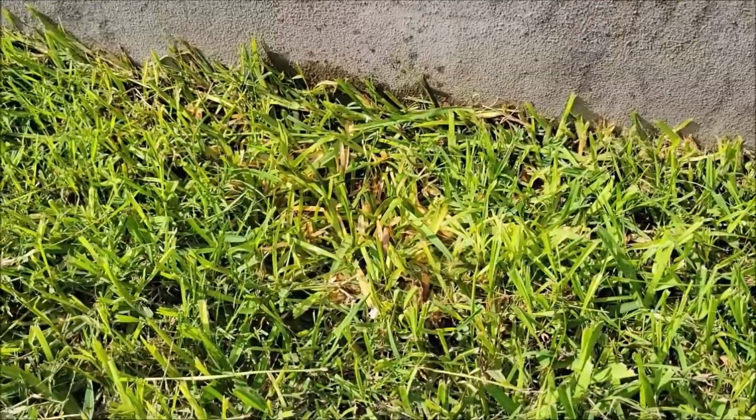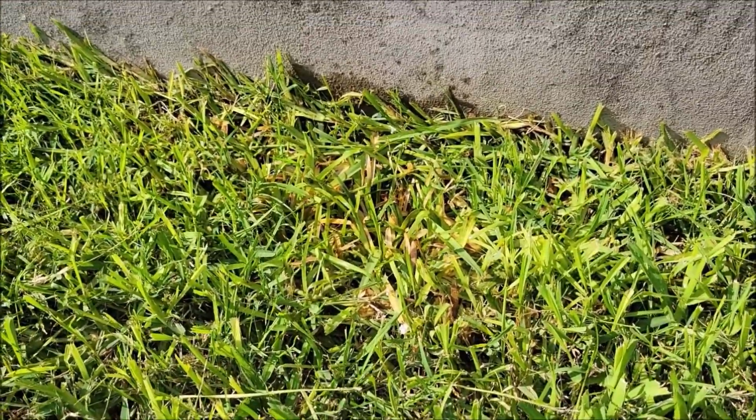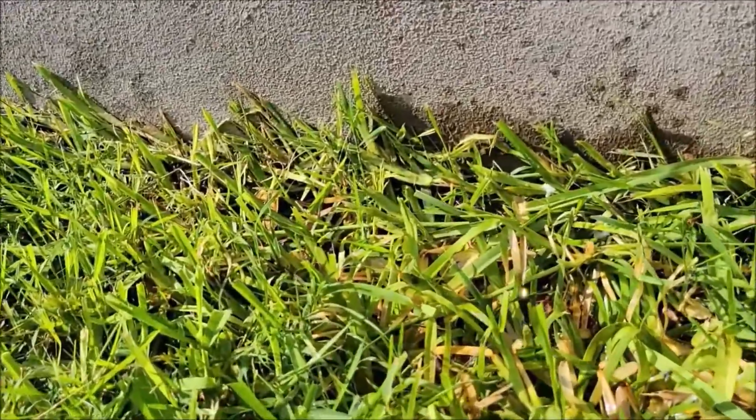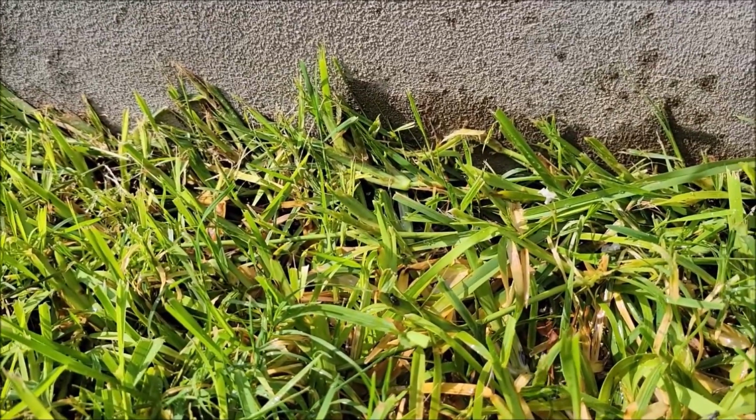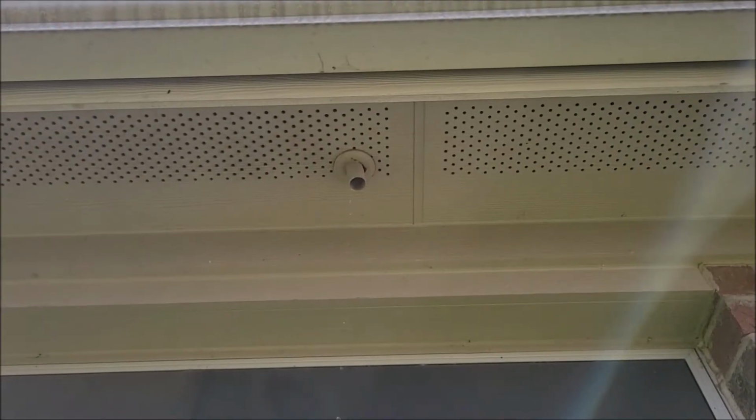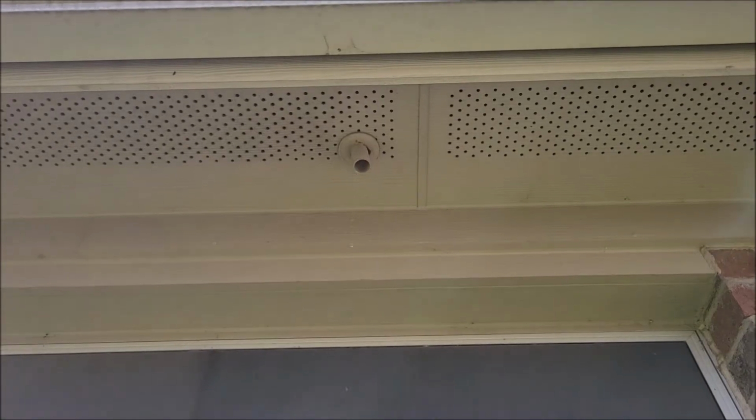Now, if that drain clogs, it fills up a little more water in that pan, which then gets to your secondary drain pipe. And the secondary will typically drip out the side of your house like this, and it will drip down basically onto the grass. Like this is just dripping in this spot in the grass. And if you can hear it, it's coming down pretty good. We know what the problem is now, so how do we fix it? Let me go show you how to do that.